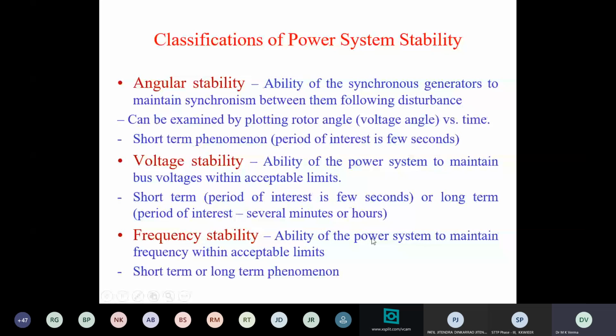Frequency stability is the ability of our system to maintain frequency within acceptable limits. This may also be a short-term or long-term phenomenon. We talk about frequency stability as related to some part of the system. For the Indian system, frequency has to be 50 hertz. So there is some acceptable range. Beyond that, if frequency goes, then there may be danger of instability. This may cause failure of the grid, which you see occurring in the system. Suppose frequency has gone down to say 47 or 47.5 hertz. This is too low, and then there may be failure of the grid due to the frequency crossing the acceptable limit. So frequency stability is the ability to maintain frequency within acceptable limits.